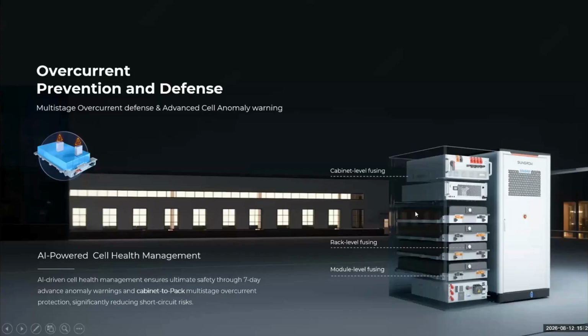Between these two parts there is an isolated design, so the cabinet can support the IP55 protection level, suitable for outdoor installation, and also the capability of overcurrent prevention. There are 3 levels in the modular design, for the racks between module to module for the whole battery module, and also for the whole racks connected to the DC side at the PCS. There are a total of 3 levels of DC fuse protection under the electrical circuit.